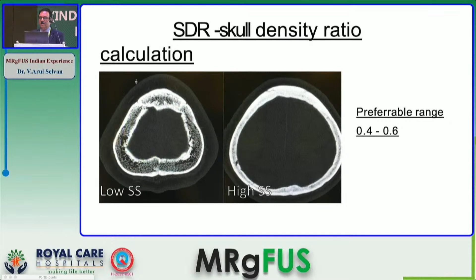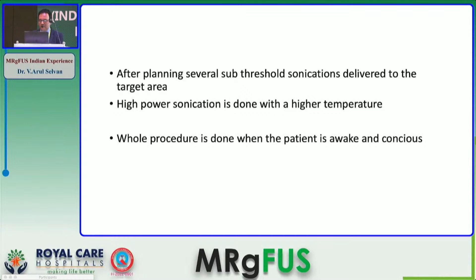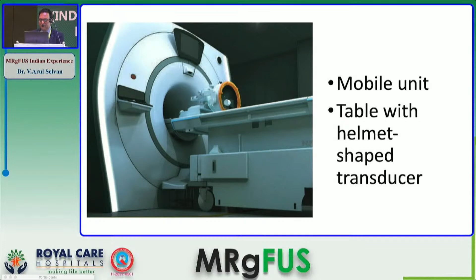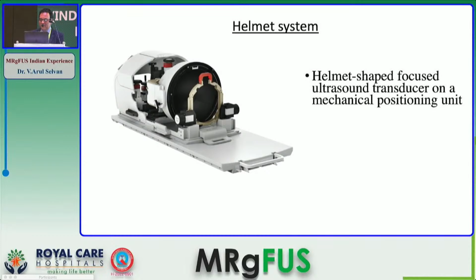After planning, several subthreshold sonications are delivered to the target area. The high power sonication is done only after that, with a higher temperature. The whole procedure is done while the patient is awake and conscious so that they can communicate very well. This is a 3 Tesla MRI; it can be done only in 3 Tesla. It's a mobile unit table with a helmet-shaped focused ultrasound transducer on a mechanical positioning unit.